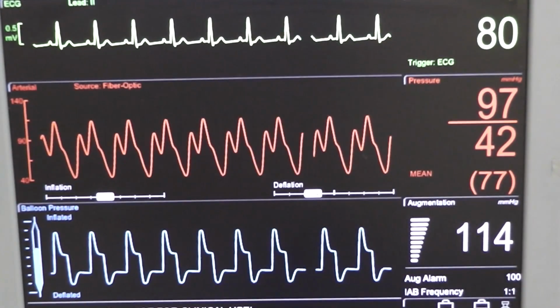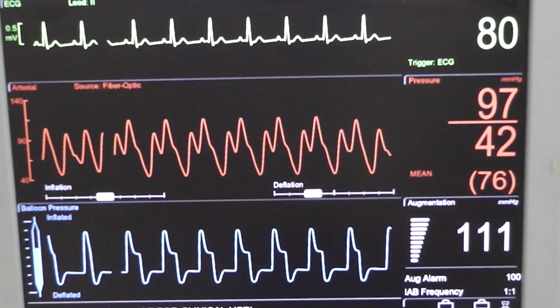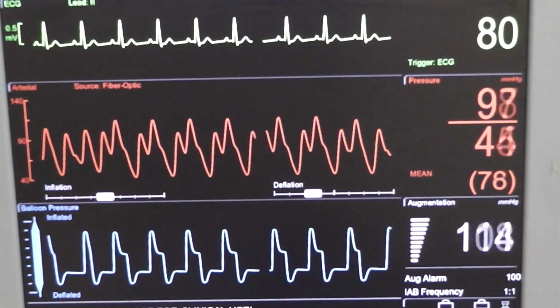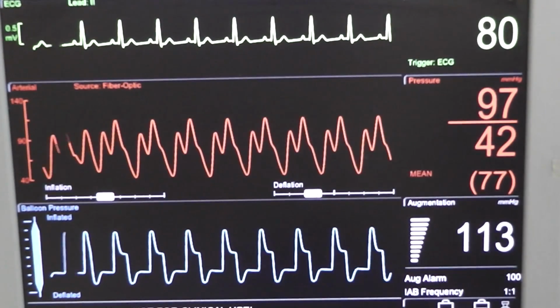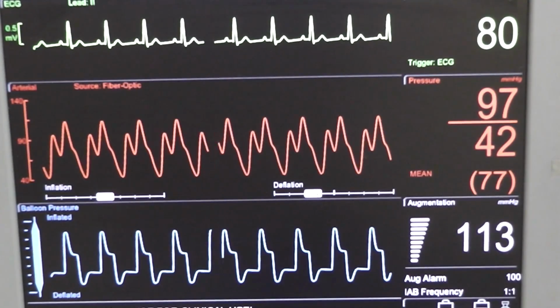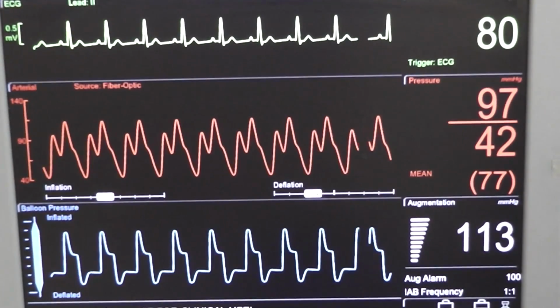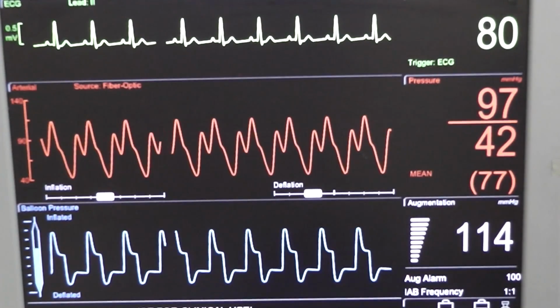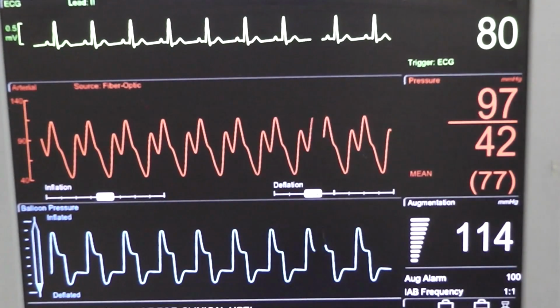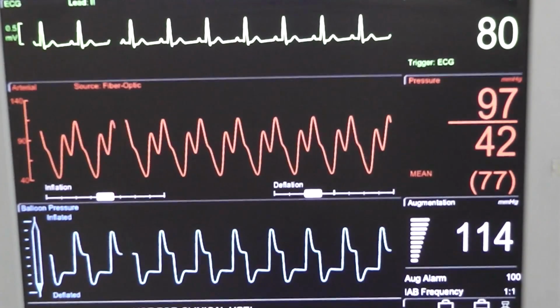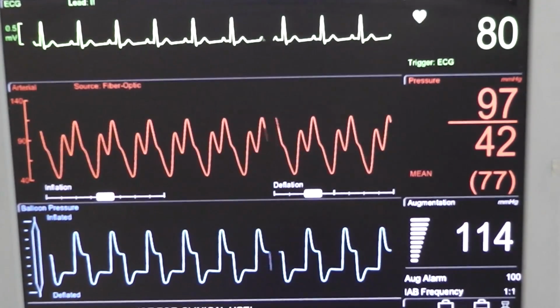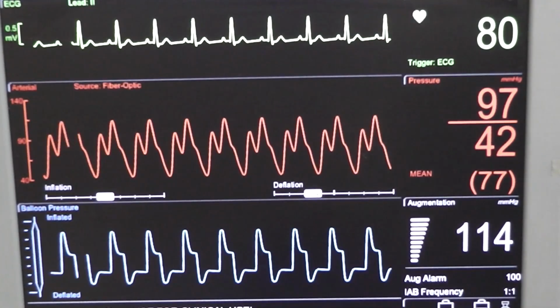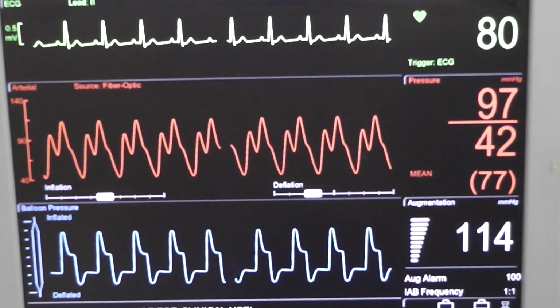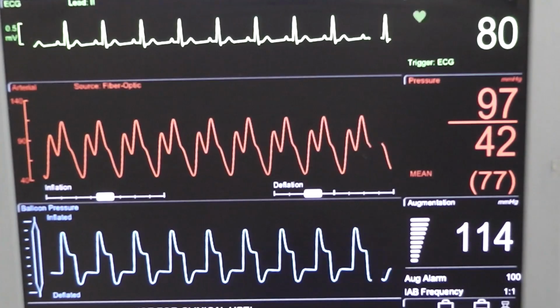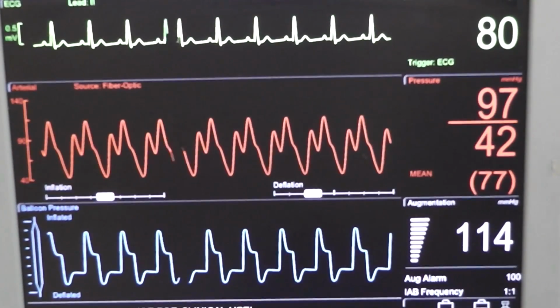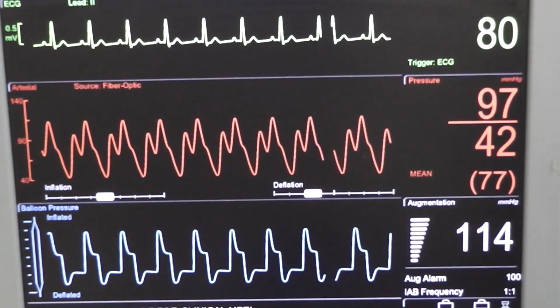Occasionally, however, we have a patient with some type of an arrhythmia. Typically it's going to be an atrial fibrillation where there isn't an equal R to R interval. And the way these machines work is they have a sensed trigger point based off of the ECG, and then it calculates a time elapse for the deflation portion. So if a patient has atrial fibrillation, the inflation portion is still going to work correctly. It will still sense the dicrotic notch in the arterial pressure waveform. That will work just fine, but the deflation portion is going to be variable and will have a difficult time with that.